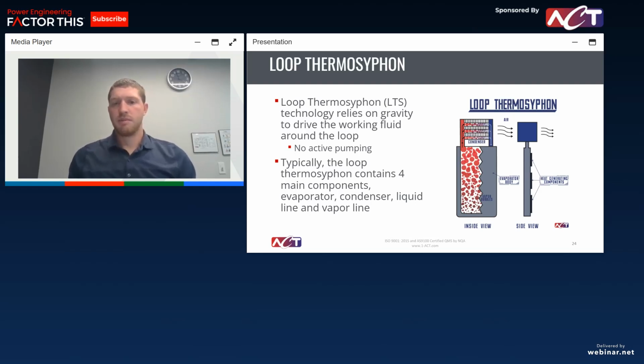So, an overview of loop thermosyphon. Like I said, it's relying on gravity. So the one major advantage here is there's no active pumping. So you're not having a mechanical component that could fail. You're not having the power consumption of that pump. Gravity is doing all the work for you. So when we're looking at a loop thermosyphon, we have four main components. We have an evaporator, a condenser, a liquid line, and a vapor line.